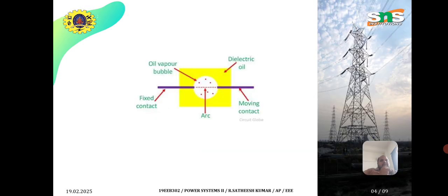This is what happens inside the oil circuit breaker. You could see when the fixed contact and moving contact open, oil vapor bubbles are produced. Those bubbles get suppressed in the dielectric oil. A huge amount of heat is also produced, and that heat makes the oil lose its dielectric property after some time. So we have to periodically check the dielectric strength of the oil. If it loses its dielectric strength, we have to change the oil so that the reliability of the circuit breaker is maintained.